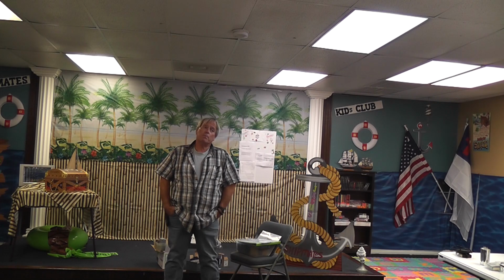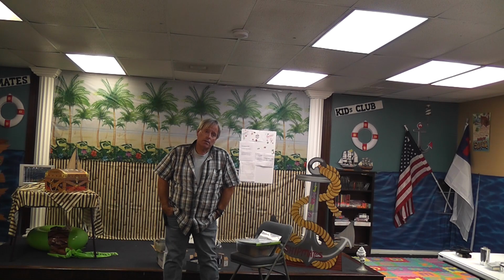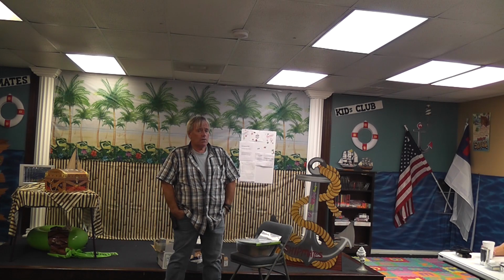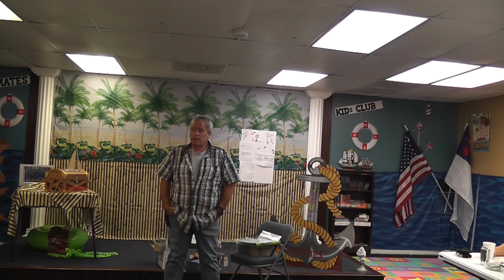Yep. The easy way to battle around that is, okay, you're going to take out copper that's twice as thick of a wall as the one you're putting in. And the copper you're taking out is round. The copper you're putting in is oval. But it's supposed to be round. If it's not round, you're not moving the volume of refrigerant. Right. You're not bringing the oil back to the compressor. And you're going to smoke the compressor for lack of oil.